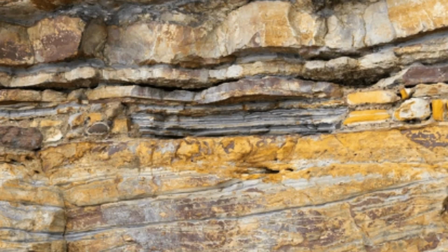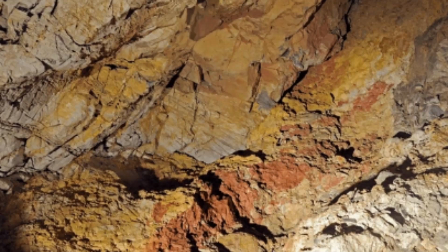Factors affecting sedimentation. Particle size and density. Larger and denser particles settle faster. Fluid viscosity. Higher viscosity slows down sedimentation. Temperature. Higher temperatures reduce fluid viscosity, enhancing sedimentation rates. Particle concentration. Higher concentrations can lead to hindered settling due to interactions between particles.